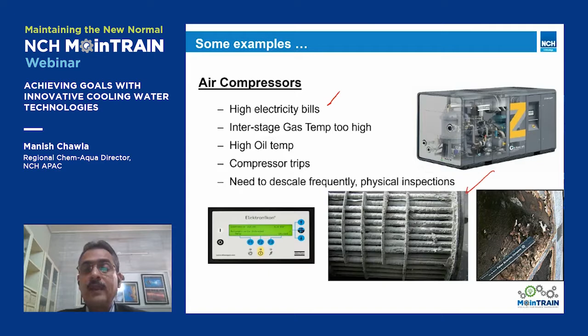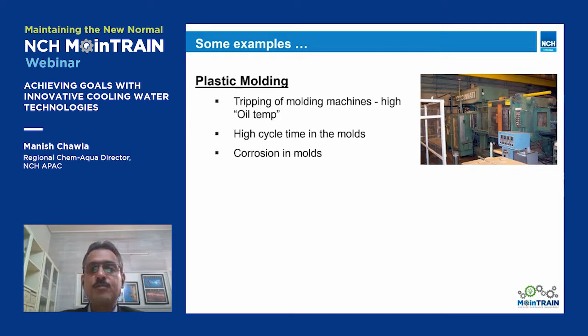In plastic molding plants, if your molding machine trips due to high oil temperature, or a mold designed for a 10-second cycle time becomes 11 seconds, you're losing production. Or when you open the molds, there's rusty brown water coming out. Oil temperature, cycle time, rotameters getting fouled, or temperature controllers showing scaling—these are all further indications.